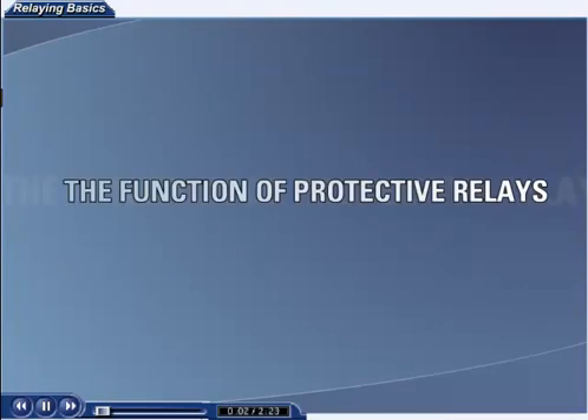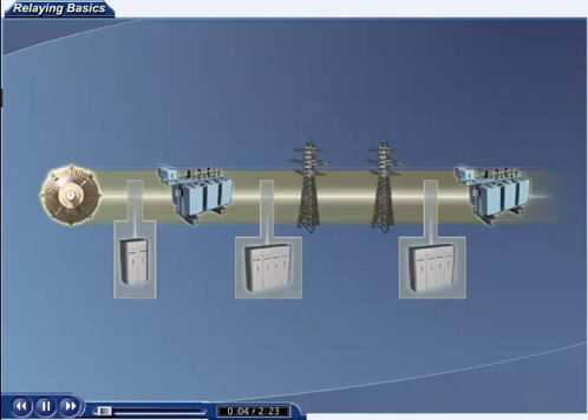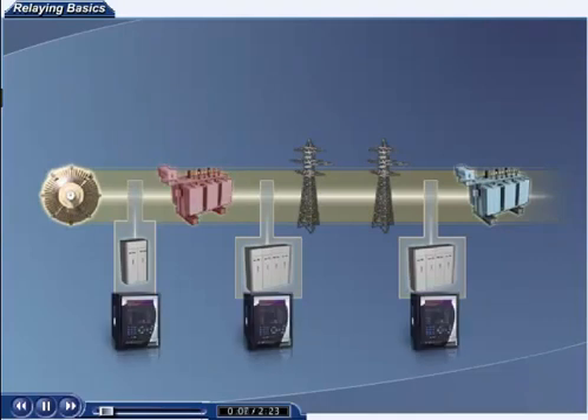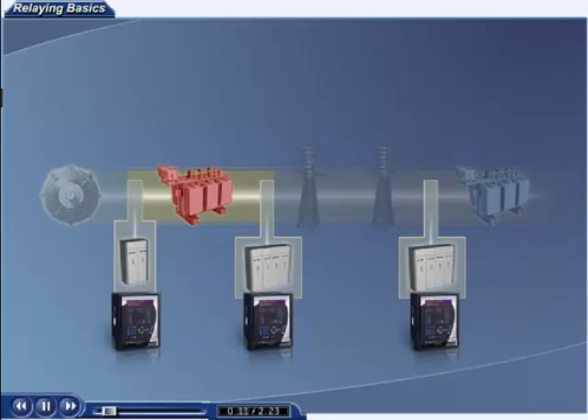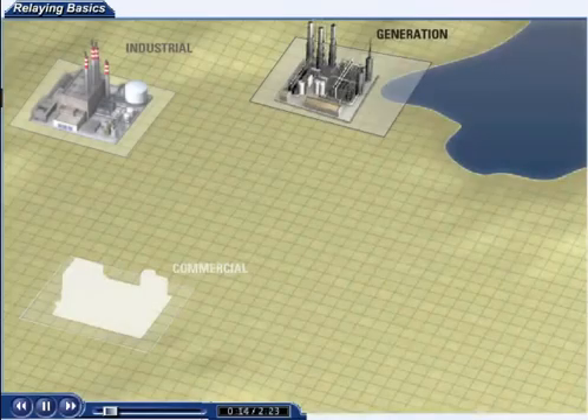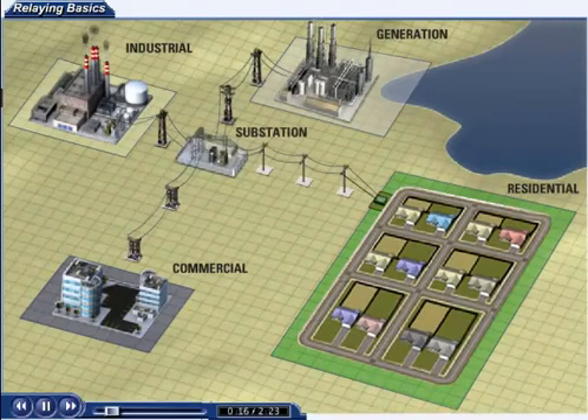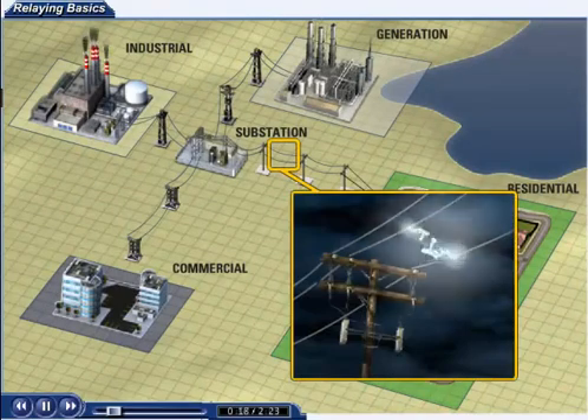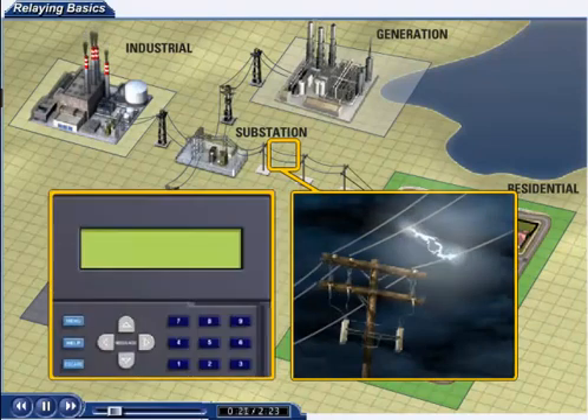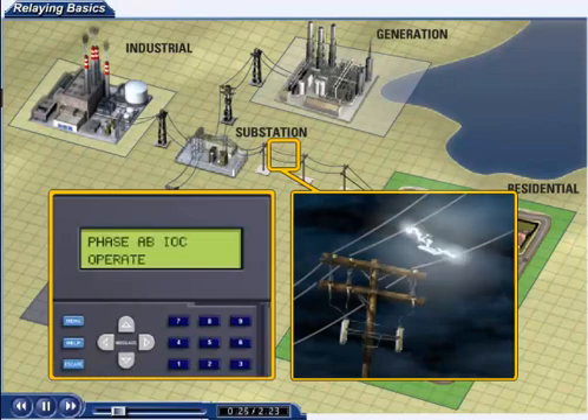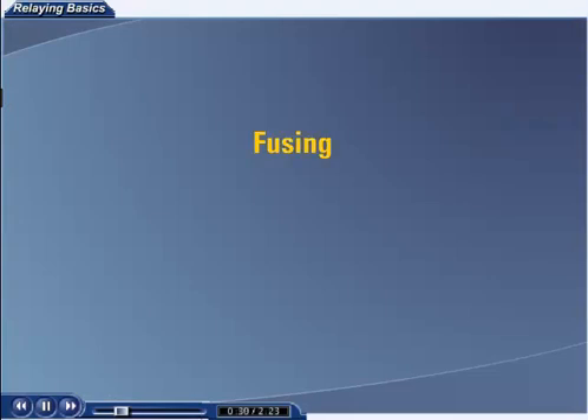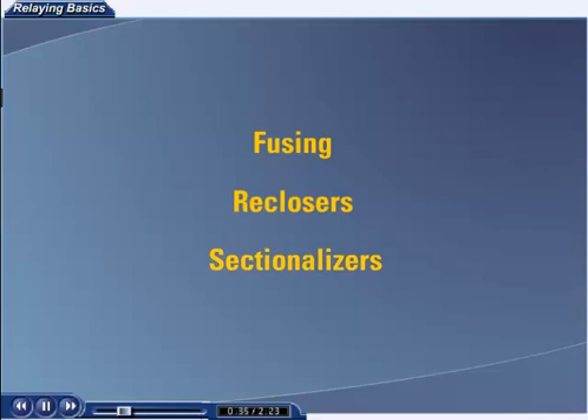The function of protective relaying is to immediately remove any component of a power system when it suffers a fault that might result in damage to property or unsafe conditions. In addition, protective relays can provide information on the locations and types of failures that occur. This information not only helps with equipment repair, but also provides the means for analyzing the effectiveness of the protection scheme. We should note that protective relays are not always part of a protection scheme. Fusing, reclosers, and sectionalizers are employed in some cases to keep costs down.